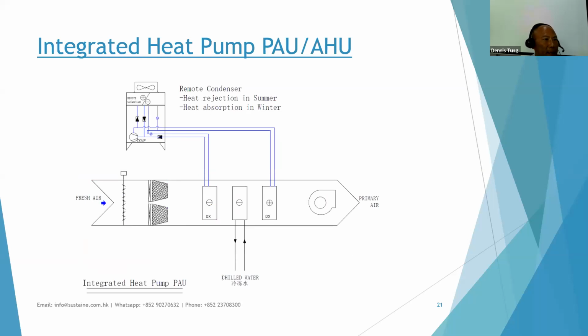Here is another example of using a heat pump to achieve energy saving. This is a fresh air unit. I would like to explain a little bit why we have this kind of unit. In Hong Kong, for example, in a sports facility or a university classroom, we have certain unoccupied periods. In these unoccupied periods, the fresh air mainly coming from the outside will be treated as usual. The temperature will be very low, so the indoor environment will be very cold. However, the relative humidity is high, because in physics, when the air temperature drops, the relative humidity goes up.